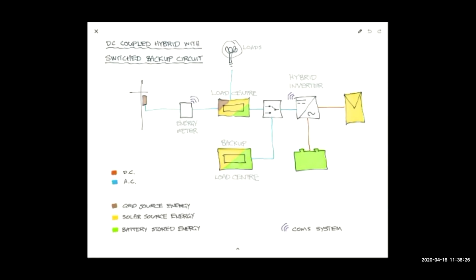Now, what I've done, sorry, electrical engineers, that's not a proper symbol for a contactor. It's just me doing a 5-year-old's drawing, but it represents a changeover switch that, when the grid fails, that little box, which is often called an ATS or automatic transfer switch, automatically isolates the inverter from the grid side. So when the grid fails, it switches and isolates from the grid, which is a requirement from a safety perspective. And it then switches its internal mode, its port, we'll call it. So this port here will go from a 4777 compliant port, which means that it will isolate within 2 seconds, to a standalone port, or SA for short. And as a standalone port, it then will become a grid-forming inverter, which we talked about earlier.